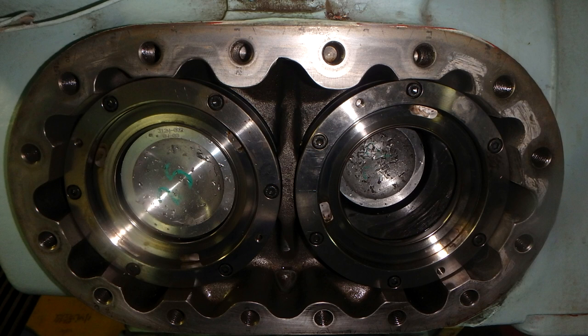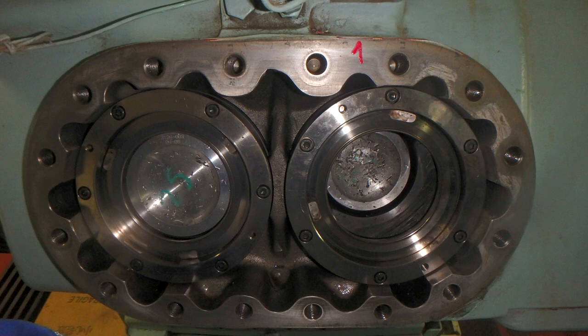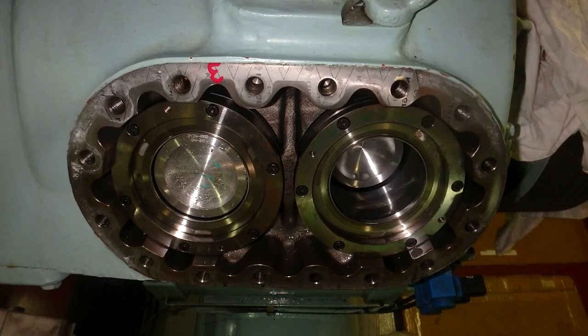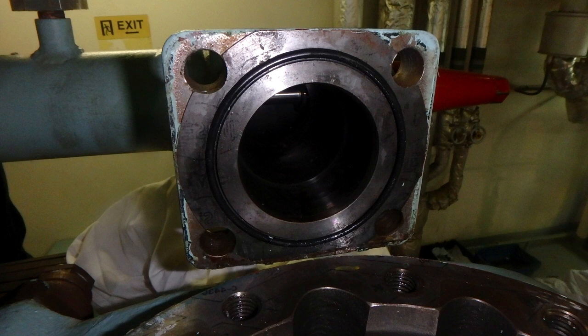The parts that have the most problems are this kind of springs, and as you can see, these small parts have already done some damage inside the pistons. So to make these surfaces a little bit better, we ground them a little bit with a fine grinding stone, so we can repair the surfaces a little, so in the future we will know what is going on, if any more damage has happened.